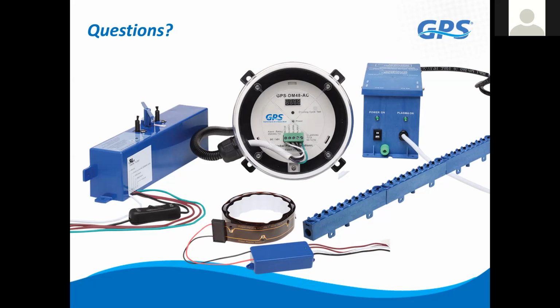Thank you. How often do the carbon needle tips need replaced? Never. The auto cleaning products, which you saw, we are estimating the product will last about 10 years. They are replaceable, but we've done cycle testing that's been well past 10 years on them. There's very little friction with the blade that goes back and forth every 3 days. And the testing that we've done has been we just have it running continuously. And there's really been no wear on the emitters or on the wiper blade.